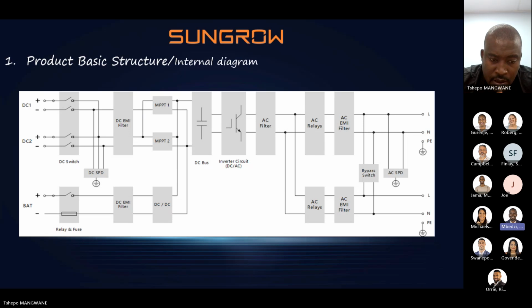I'm not sure whether you're talking about the inrush current or the permanent power. Permanent power? Let's say the client for some reason increases the power. In that case, the inverter will trip. It won't accommodate. So if it's running on 3 kilowatt and the load increases to 3.5, it will eventually trip. Okay, cool. So if it's a full hybrid system, with inverter, panels, and batteries, a 6 kilowatt inverter can take up to 8 kilowatt for 10 seconds, just to start up high demand machines.